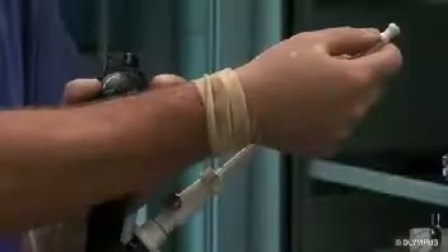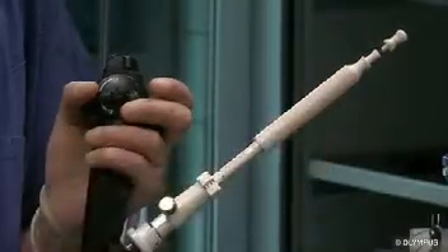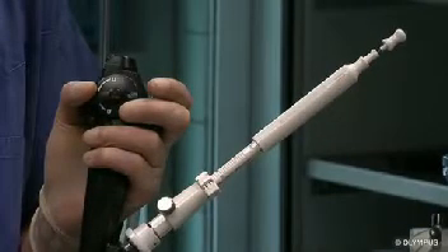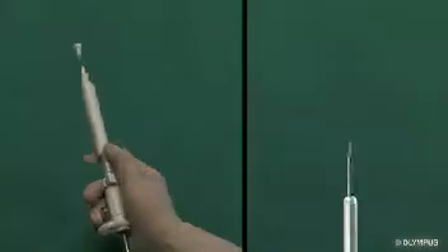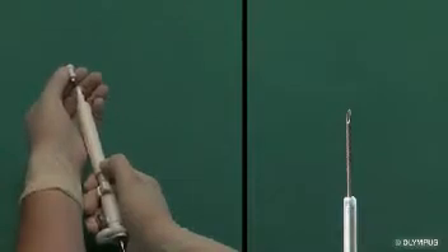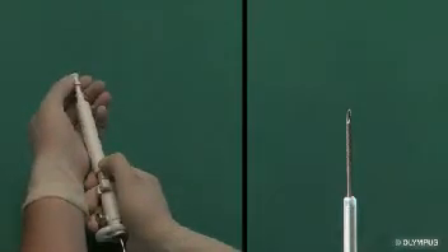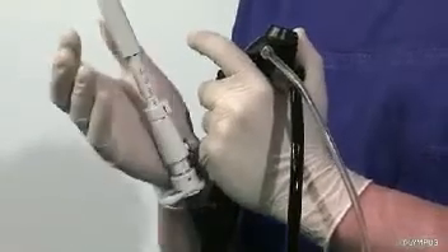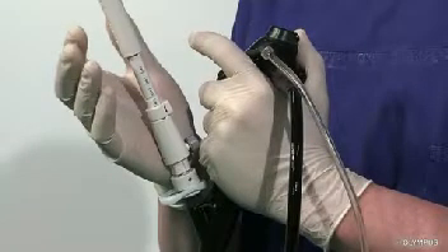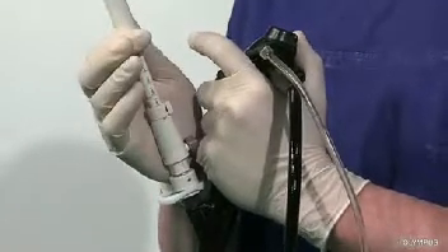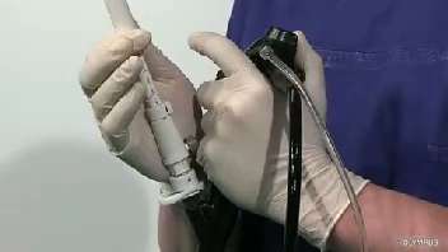The round stylet knob is withdrawn a few millimeters in order to expose the sharp needle tip. Attention! If not slightly withdrawn, the needle tip will be filled with the blunt stylet and will not allow easy penetration through the bronchial wall. Place the palm of your free hand on the connector section of the needle. Place thumb and index finger on the lower part of the needle slider. This hand position will allow full control of the needle movement.